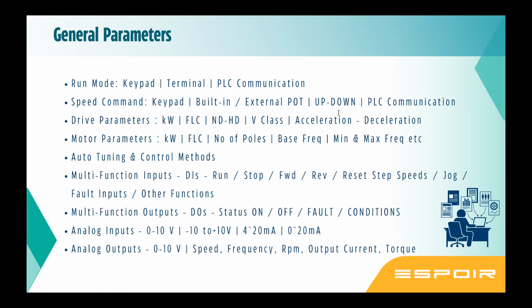you need to set the drive basic parameters: the kilowatt, full load current, normal duty or heavy duty, voltage class, acceleration time, deceleration time. So this is very important. These are the basic parameters which you need to set. Without setting that, there is always a default parameter which may not serve the purpose for you in a given environment. So you need to change the parameters from factory default to a user requirement.